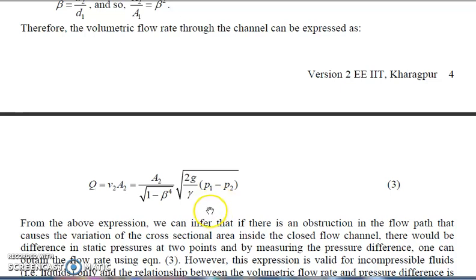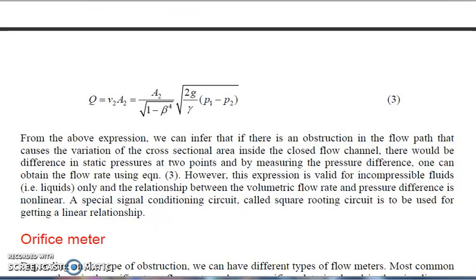We can measure the flow by measuring the pressure difference at two different sections of a pipe. This is the phenomenon giving us the idea of how flow measuring instruments work. From the above expression, if there is an obstruction in the flow path causing variation of cross-sectional area inside the closed flow channel, there will be a difference in static pressure at two points, and by measuring that pressure difference we can obtain the flow rate. The formula derived is for incompressible fluids, and the relationship between volumetric flow rate and pressure difference is non-linear — it has an under-root (square root) relation.